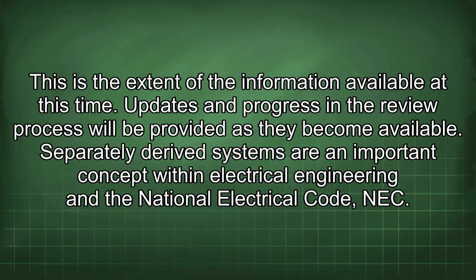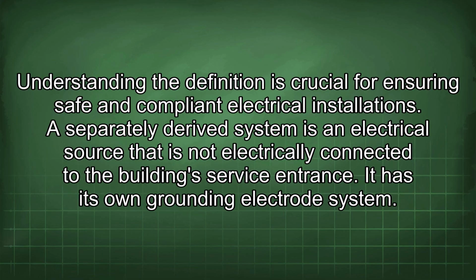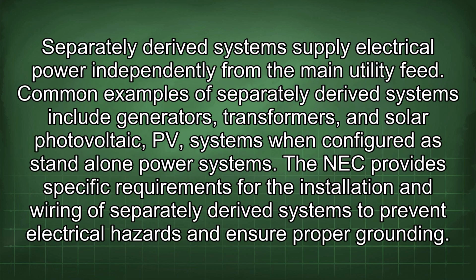Separately derived systems are an important concept within electrical engineering and the National Electrical Code (NEC). Understanding the definition is crucial for ensuring safe and compliant electrical installations. A separately derived system is an electrical source that is not electrically connected to the building's service entrance. It has its own grounding electrode system. Separately derived systems supply electrical power independently from the main utility feed.